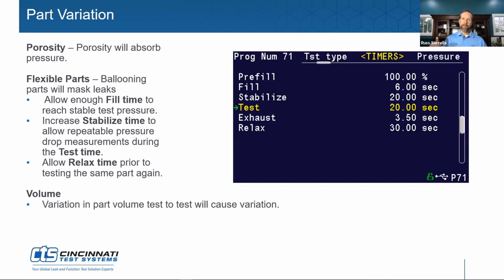And that's because the adiabatic temperature effects are being eliminated, and that masking of porosity, those different variables, are all being normalized because we're continuing to hit the start button over and over again. So that is something that is common, and customers see that and say, oh my gosh, my test isn't repeatable. But the reality is that's not the case. It is the fact that you are not testing under the same conditions with which you calibrated. Yep, absolutely.